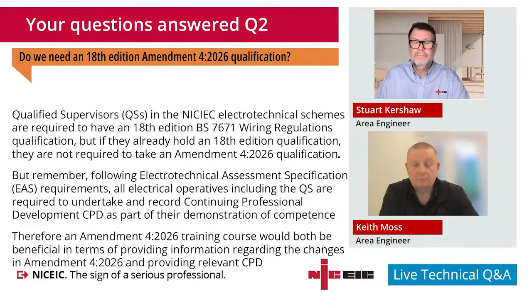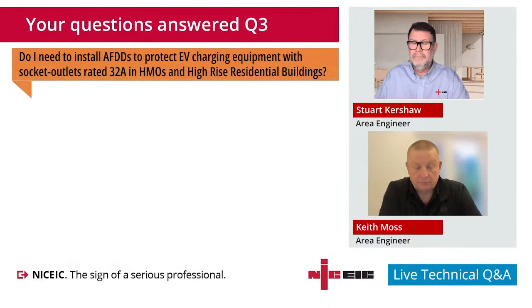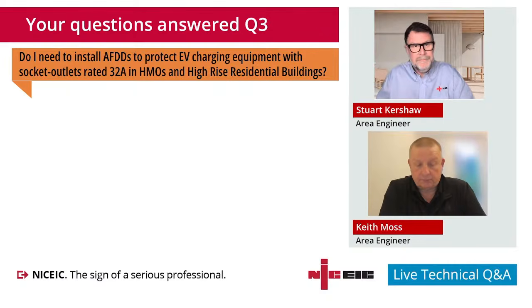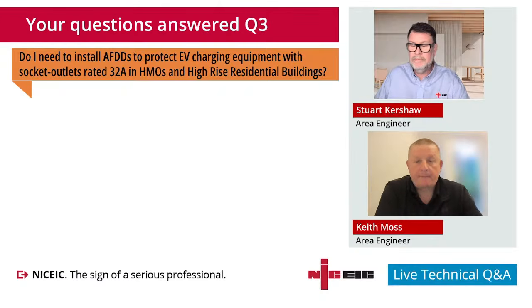So next one, this is a good one regarding the change. Do I need to install AFDDs to protect EV charging equipment because it's got socket outlets rated at 32 amp, and it's in an HMO or a high-rise residential building? So do I need to fit AFDDs in those instances, Keith?